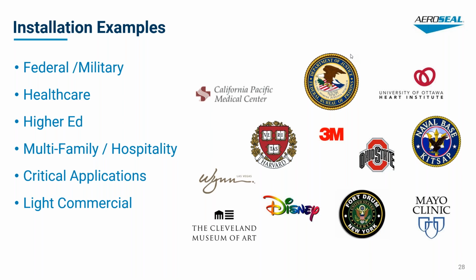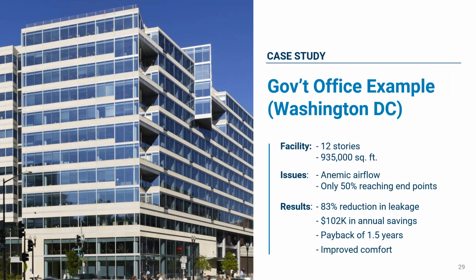We wanted to spend time on a couple specific applications. The first is a case study from an office building in Washington, D.C., where we partnered with Sodexo. It was a big building to seal — 12 stories, almost 1 million square feet — and their primary issue was anemic airflow, with only 50% of treated air reaching its endpoints. Once Aeroseal was introduced and completed, we achieved an 83% reduction in leakage and over $100,000 in annual savings, providing an aggressive payback of 1.5 years. More importantly, the people working at the ends of those duct runs had much better air quality.